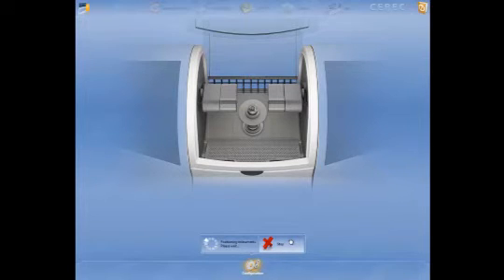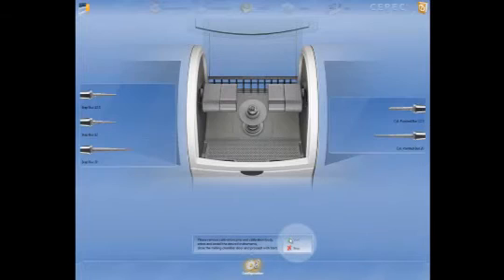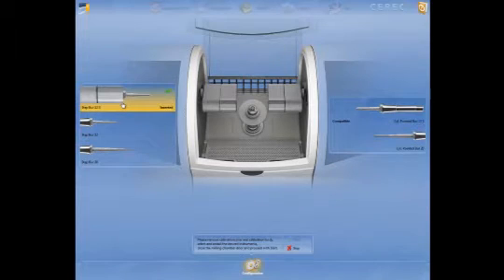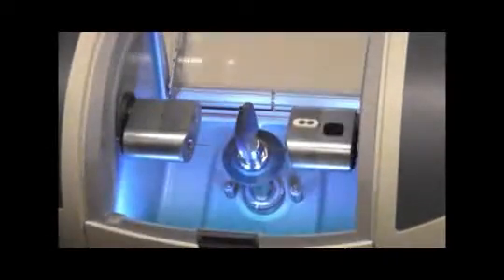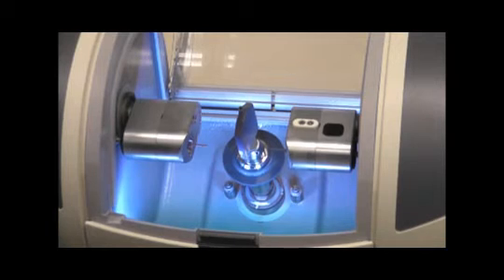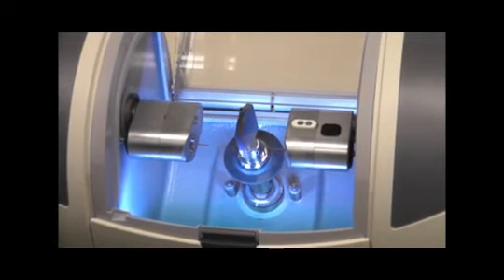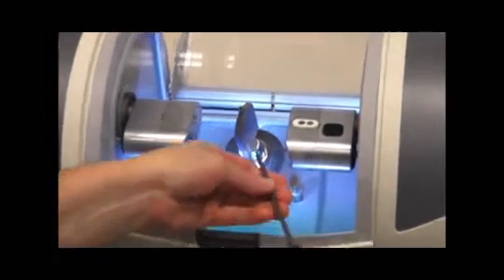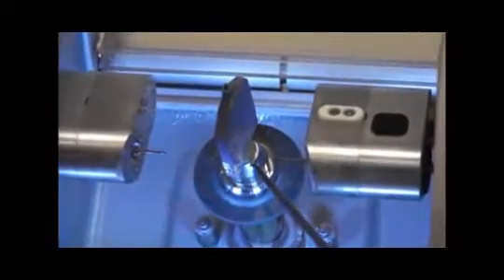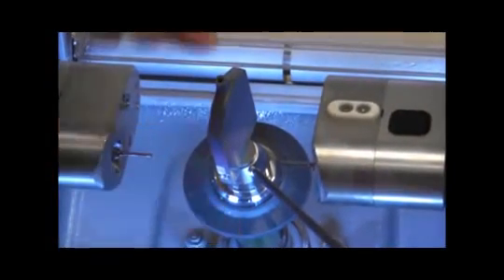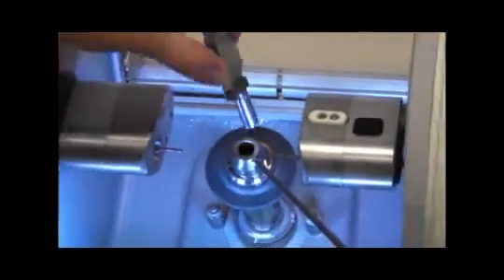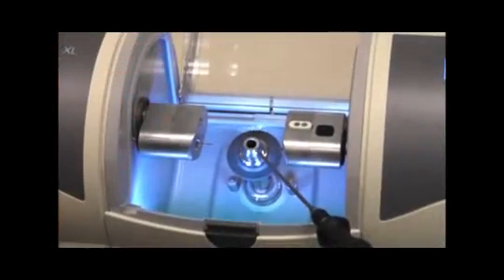In the software, click and highlight the burrs that will be replacing the calibration pins. Then remove the calibration pins from the MCXL unit. Open the MCXL lid and use the provided torque screwdriver to loosen the screw on the block chuck to remove the calibration specimen. Once the calibration specimen has been removed, it is easier to access the calibration pins to remove them.